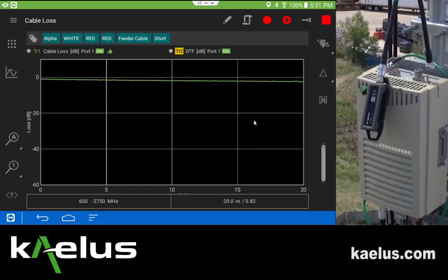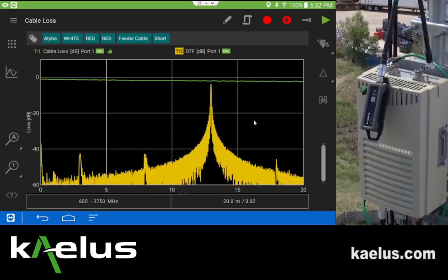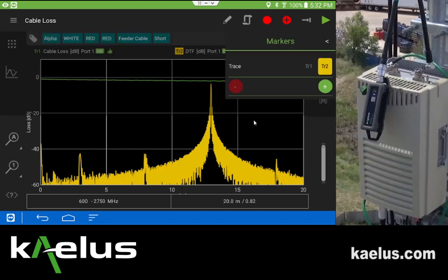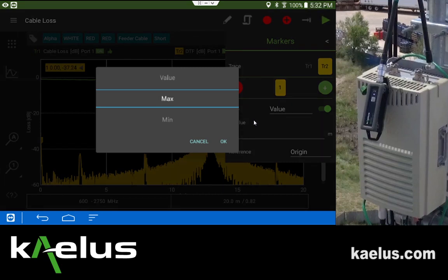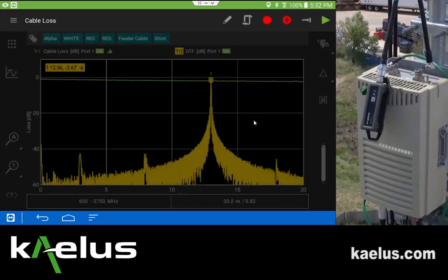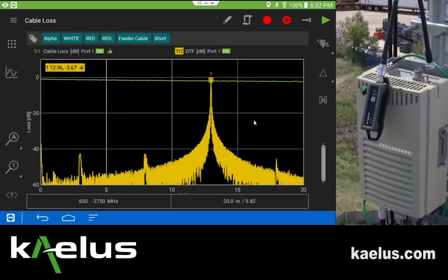We now sweep the data. As before, it will first measure trace one and then follow up with a measurement for the distance to fault calculation on trace two. We have a great deal of information — at the end of the line there is a short circuit. Creating a marker by long-holding the marker icon brings up the option of adding a max marker, and we find that our cable length is indeed 12.96 meters. With the short circuit, this shows return loss very nearly equal to twice the cable loss, which is a good indication.